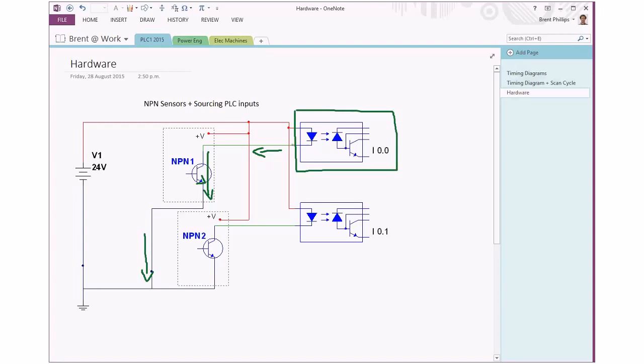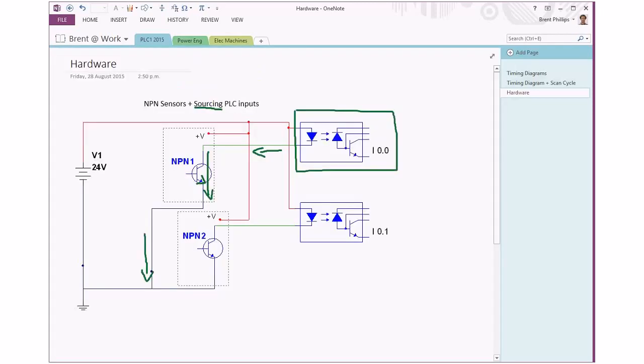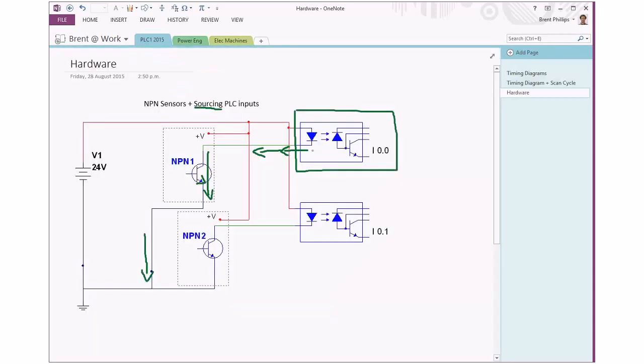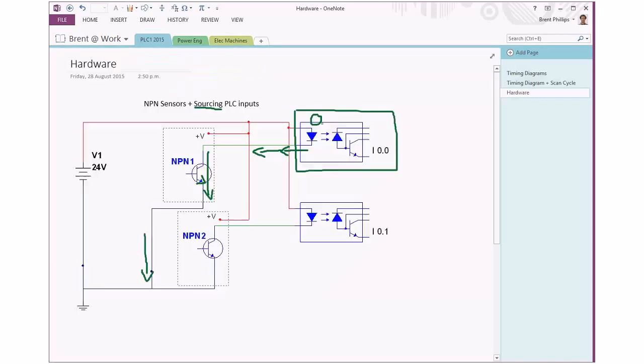Because of the direction of this current, this type of PLC input is known as sourcing. You can remember that it's sourcing because here's our PLC input in this green box, and the current is flowing out of here. This would be the terminal on the PLC - in this case it's number zero because we're looking at input number zero. Down here we've got input number one, so this would be input number one on the circuit.